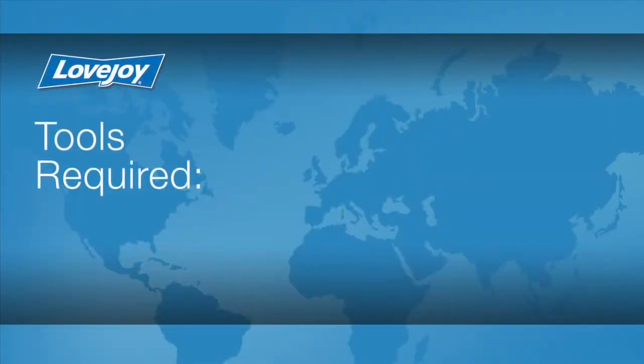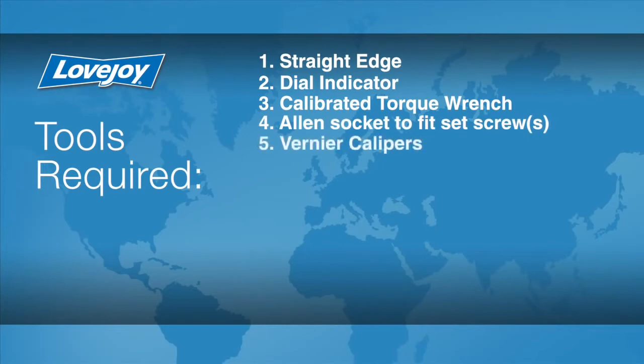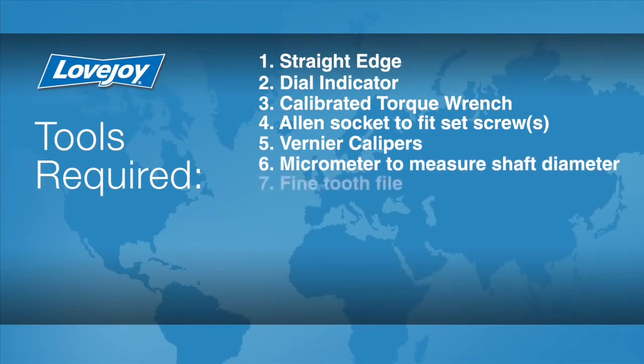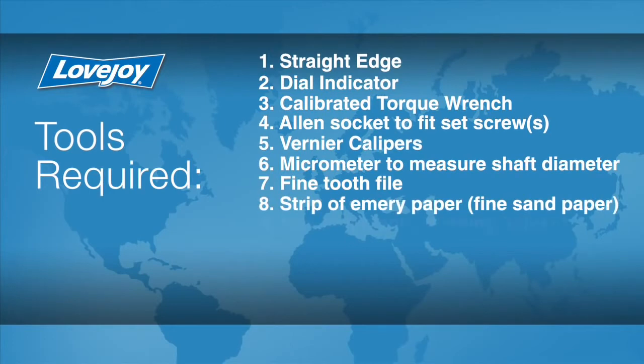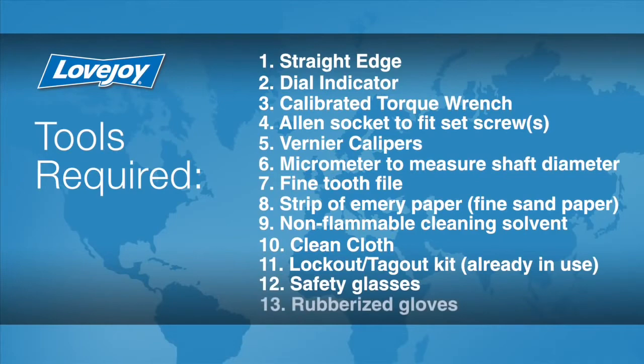Let's look at the necessary tools we will need to perform this installation: a straight edge, a dial indicator, a calibrated torque wrench, Allen socket to fit the set screws, vernier calipers, a micrometer to measure the shaft diameter, a fine tooth file, a strip of emery paper, non-flammable cleaning solvent, a clean cloth, lockout tagout kit, safety glasses, and rubberized gloves.